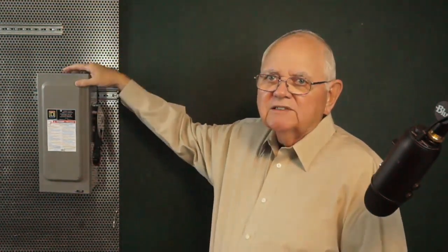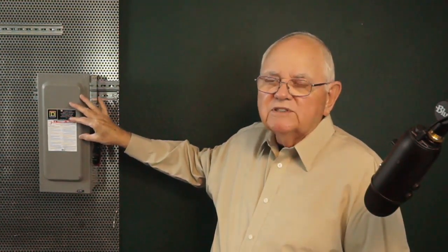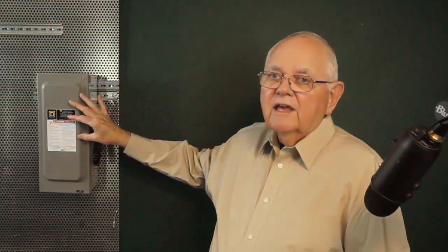It covers from the point of connection to the supply, to the electrical equipment of the machine. So if this disconnect is supplying our machine, the National Electrical Code applies all the way into the disconnect. Then there are certain provisions for this disconnect, if it's used on industrial machinery, where NFPA 79 applies from the disconnect on into our electrical equipment. We're going to talk about some of those requirements.